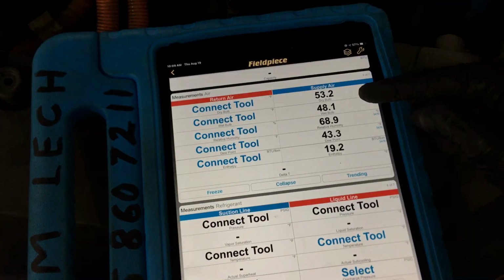There we go. I'm still waiting for this, it's starting to go down, the suction line. It's still staying up there in the 60s. We're coming out the dash at 50. So that was heat pump mode, it was literally heating using refrigerant.